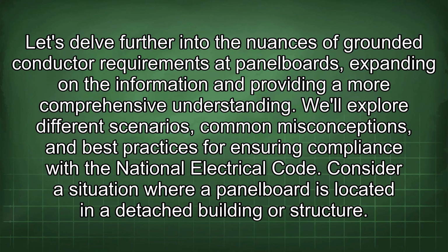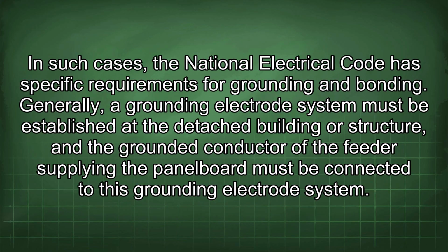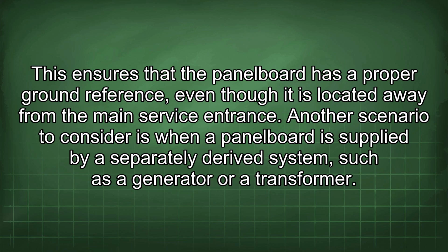Let's delve further into the nuances of grounded conductor requirements at panel boards, expanding on the information and providing a more comprehensive understanding. We'll explore different scenarios, common misconceptions, and best practices for ensuring compliance with the National Electrical Code. Consider a situation where a panel board is located in a detached building or structure. In such cases, the National Electrical Code has specific requirements for grounding and bonding. Generally, a grounding electrode system must be established at the detached building or structure, and the grounded conductor of the feeder supplying the panel board must be connected to this grounding electrode system. This ensures that the panel board has a proper ground reference, even though it is located away from the main service entrance.